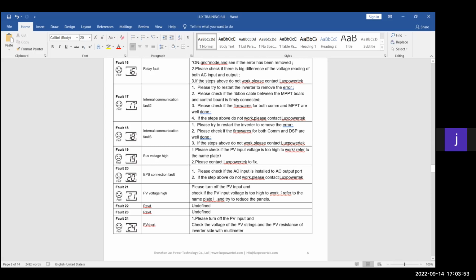There are certain batteries that we're having a problem with here and there on certain inverters, where the Lux team usually just does an update and a setting or two, and 99% of the time it's fixed. We have systems here and there that are slightly more sensitive to that, and they are working on updates to improve this bus voltage high. But the bus voltage high is something that happens as soon as your panels usually charge your batteries and the battery's BMS stops. And it's usually where a battery has an imbalanced cell, so the voltage goes higher on one cell and then it stops at the earliest stage in the charging cycle.